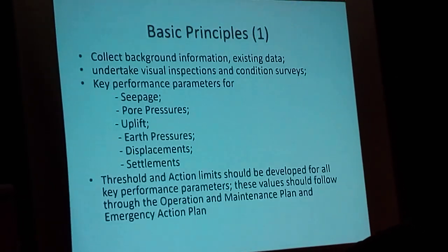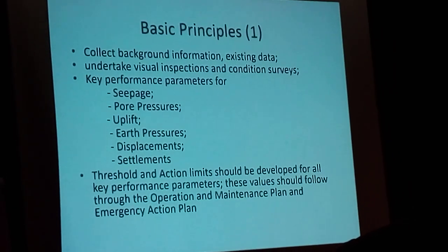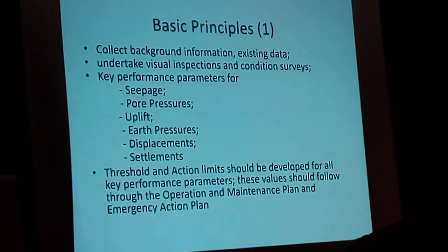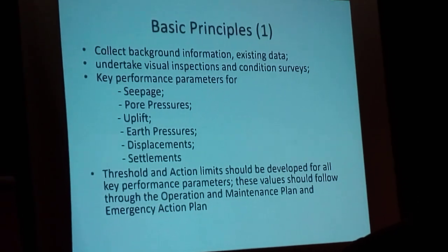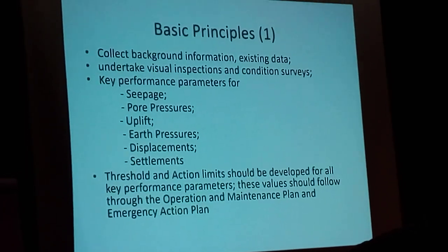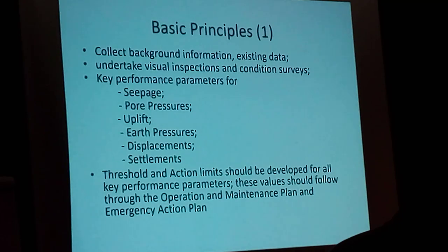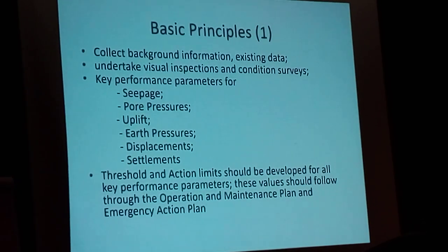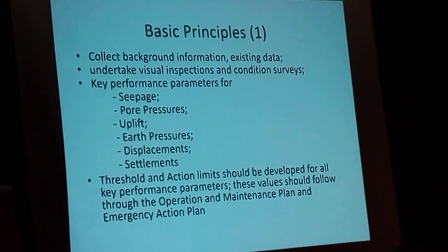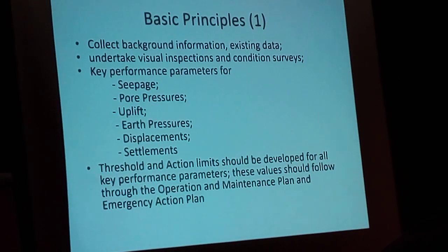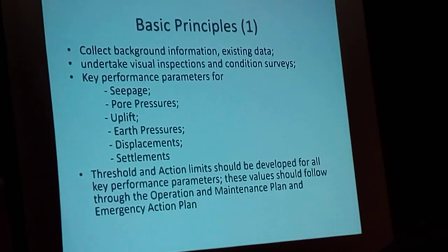The basic principles are: we collect background information and existing data, undertake visual inspection and condition surveys. The key performance parameters, as you have heard, are pore pressures, pore water pressure, displacement and settlements. What is important is to have threshold and action limits — these should be developed for all key performance parameters, and these values should follow through into the operation and maintenance plan. So it's the monitoring, the threshold values, the action plan — all part of what I call instrumentation.